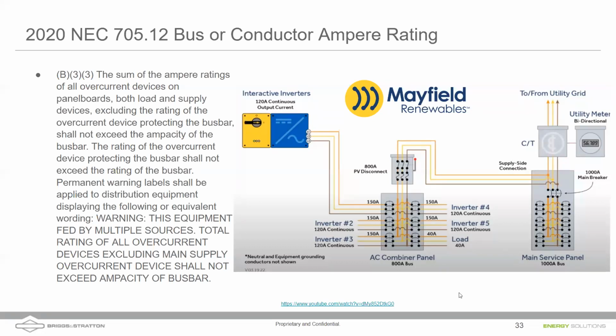Essentially what this means is that you've got an 800 amp bus bar on a panel, and as long as the sum of all of the amp ratings of those overcurrent breakers, both load and supply devices, don't exceed the ampacity of that bus bar, you're okay. So I can backfeed as much power as I want, as long as the sum of those backfed breakers and the sum of any loads that are in the panel don't exceed that 800 amps.